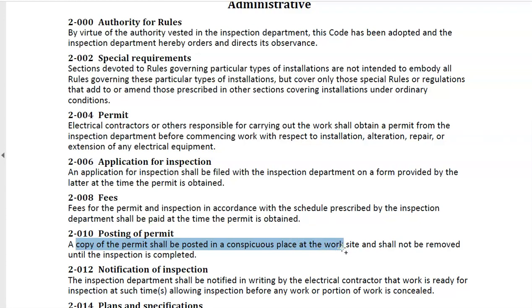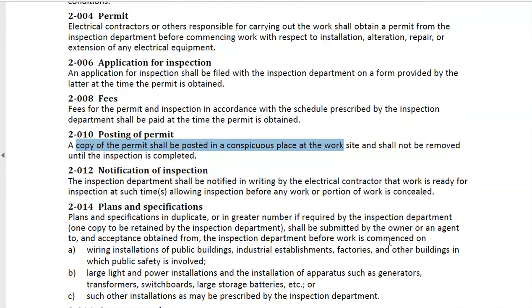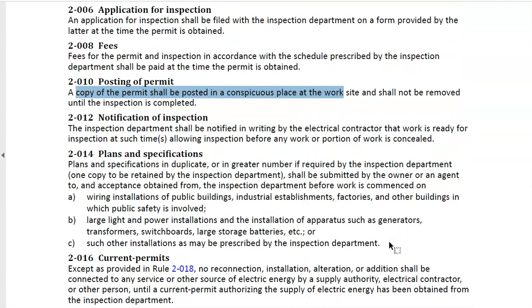You need to have a copy always posted so that anybody — not just the electrical inspector, but civil inspectors or anyone — should be able to walk up and confirm it's a legal job. Plans and specs are supposed to be submitted to the inspection department, which is Technical Safety BC here in our province, by the owner or agent before work is commenced. You have to submit plans for public buildings, industrial establishments, factories, or other buildings in which public safety is involved.